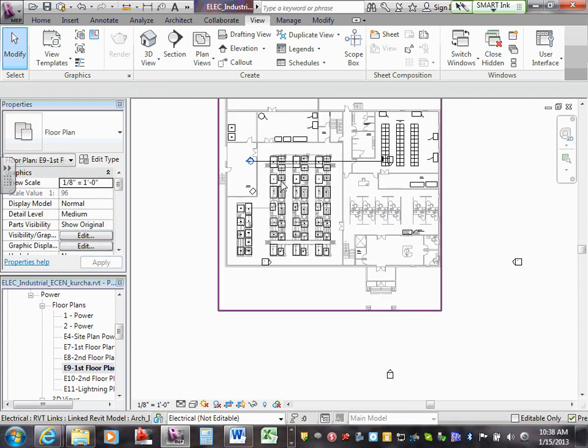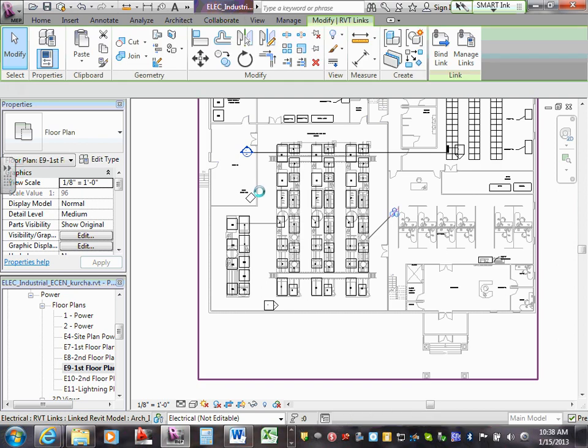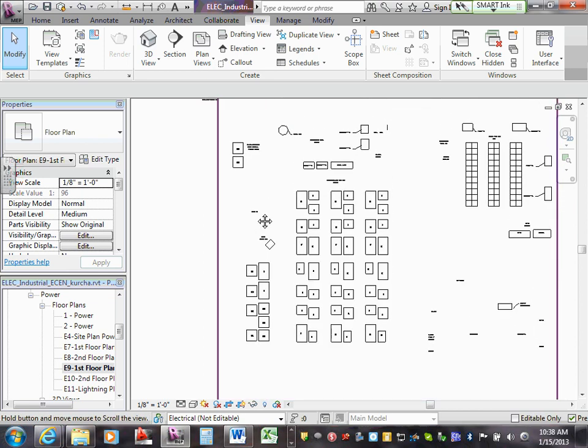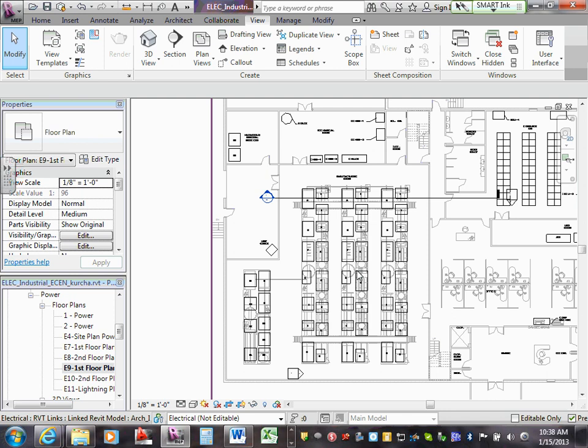Let's go into the manufacturing area. This you're gonna set up just the same way as basically the paging speakers, except you can do column mounted out here, if you have them. If not, you're gonna do around the walls. And again, it's gonna be every 50 feet. Depending on the noise level, you may want to just offset every other one as a strobe, so that the visual indication is more of what they're looking for, and they'll know what to look at for the fire alarm system. The horns are just noise, pretty much, in the manufacturing area.